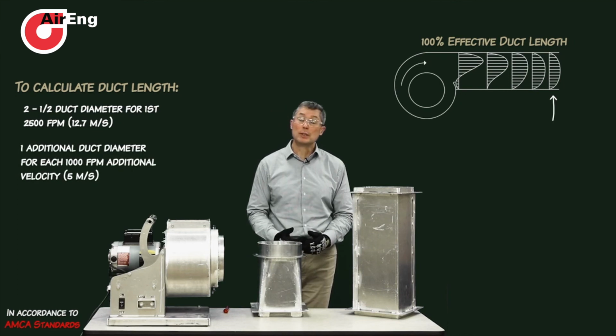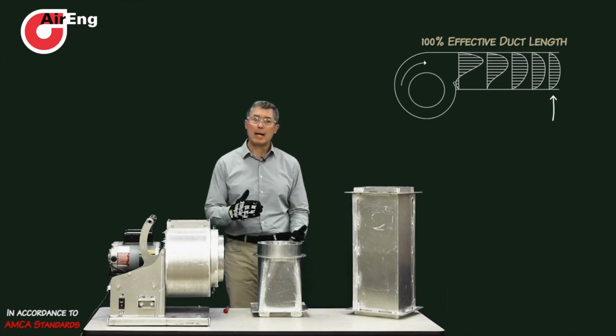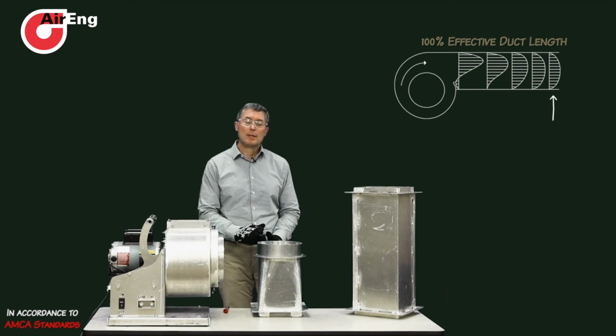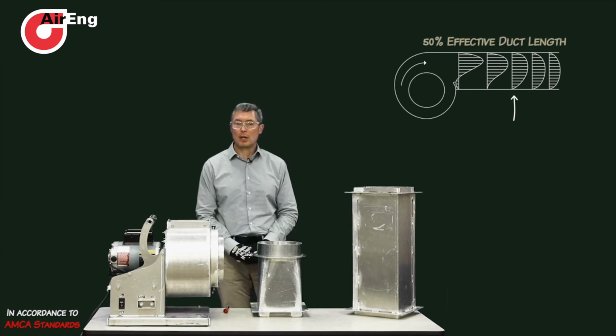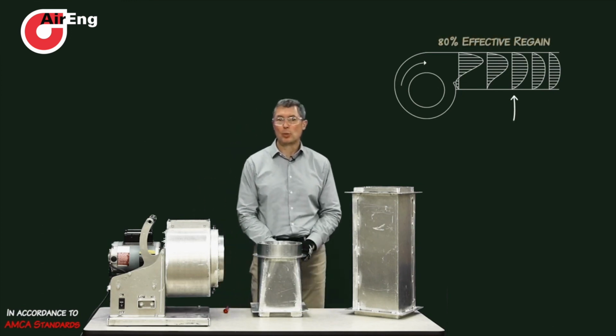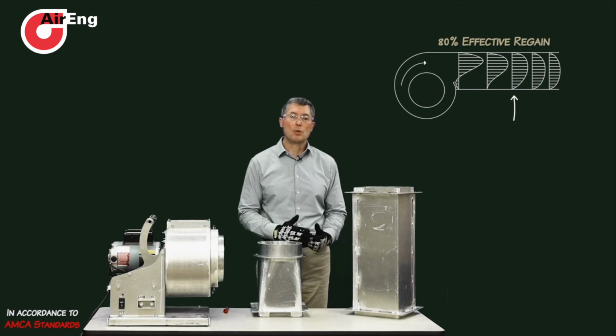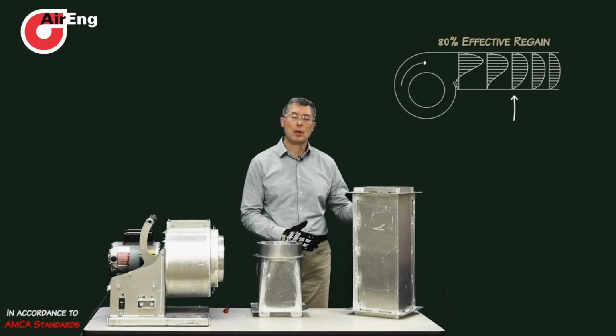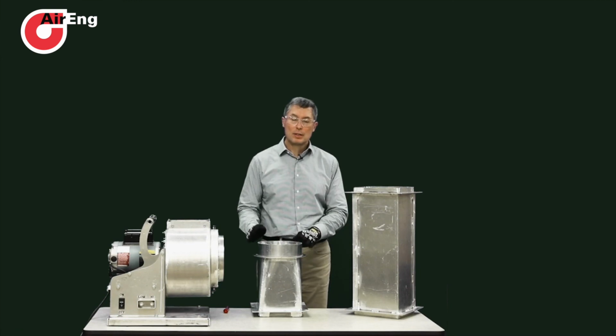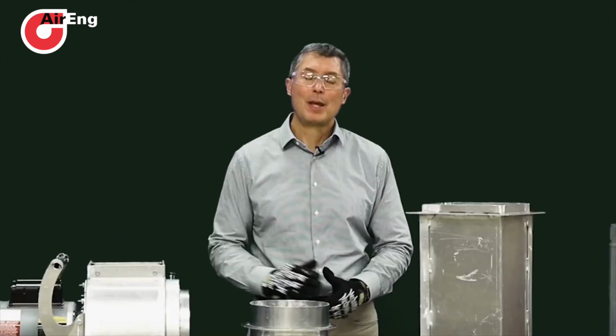It also shows in the graph or the diagram that if you have 50% of your effective duct length, you're going to get about 80% of your regain. So if you have an obstruction or some reason why you can't utilize the full length of duct, something is much better than nothing.